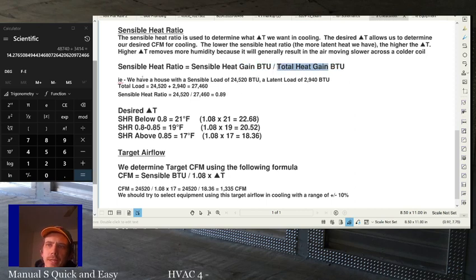All right. For example, if we have a house with a sensible load of 24,520 BTUs and a latent load of 2,940 BTUs, the total load is 24,520 plus 2,940 equals 27,460. So our sensible heat ratio would be that 24,520 sensible load, right, divided by the 27,460 total load, and that would equal a 0.89 sensible heat ratio.